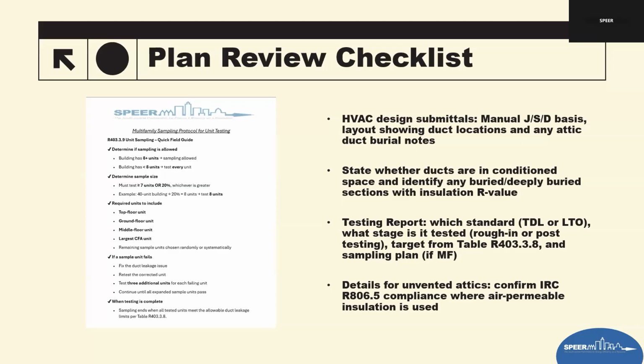And any unvented attics with air-permeable insulation, as in buried ductwork, basically doing blown fiberglass or cellulose, putting ducts in conditioned space, must also meet IRC R806.5. And just notice that those things are listed on the plans. Plan review, as we always say, is the first line of defense. These items must clearly be documented in the plans. Your field inspections must represent what is in the plans and permit documents. And then duct leakage testing will go much smoother and produce far fewer surprises if this is done clearly in the plan review in the beginning.